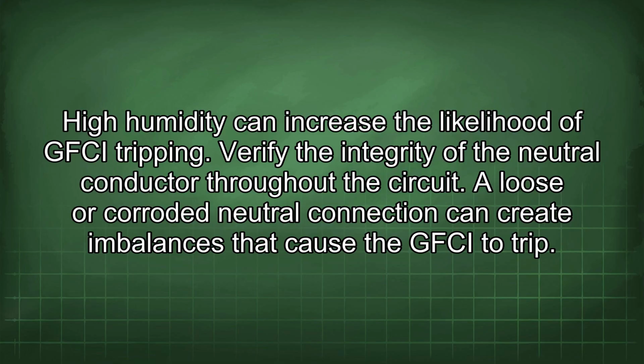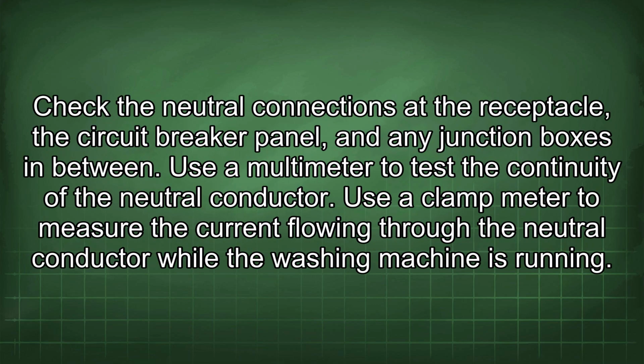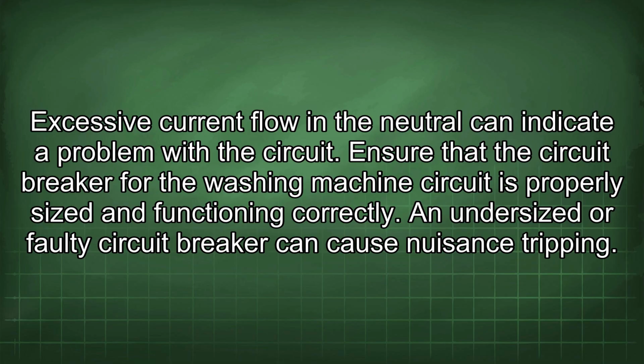Verify the integrity of the neutral conductor throughout the circuit. A loose or corroded neutral connection can create imbalances that cause the GFCI to trip. Check the neutral connections at the receptacle, the circuit breaker panel, and any junction boxes in between. Use a multimeter to test the continuity of the neutral conductor. Use a clamp meter to measure the current flowing through the neutral conductor while the washing machine is running. Excessive current flow in the neutral can indicate a problem with the circuit.